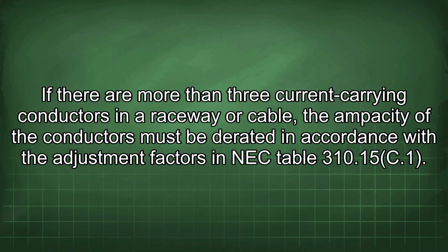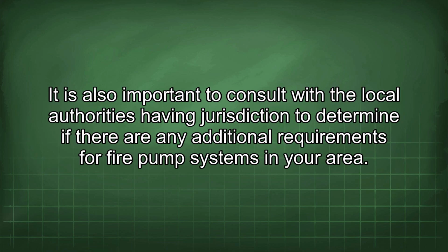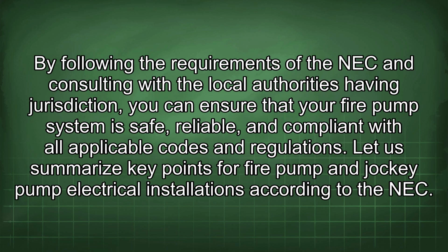If there are more than 3 current carrying conductors in a raceway or cable, the ampacity of the conductors must be derated in accordance with the adjustment factors in NEC Table 310.15(C)(1). It is also important to consult with the local authorities having jurisdiction to determine if there are any additional requirements for fire pump systems in your area. By following the requirements of the NEC and consulting with the local authorities having jurisdiction, you can ensure that your fire pump system is safe, reliable, and compliant with all applicable codes and regulations.